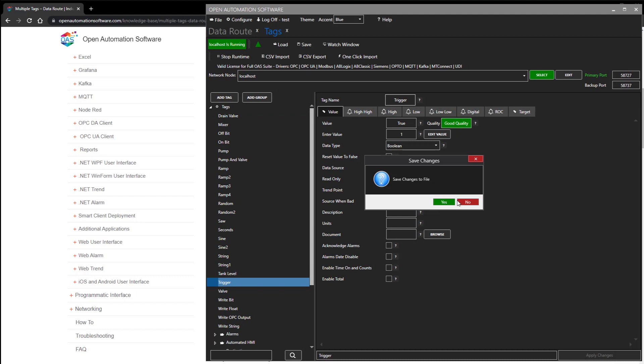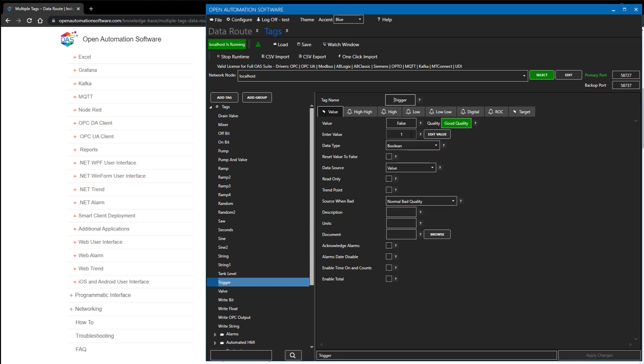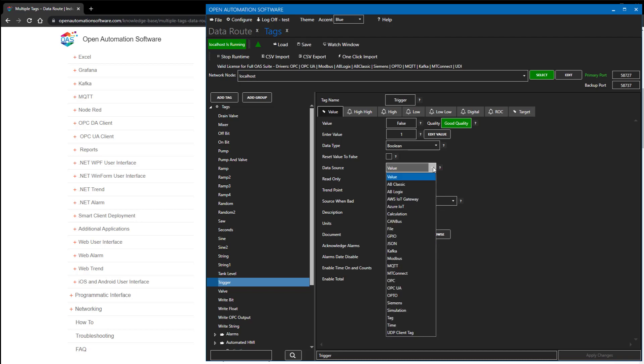Looking at the tags and the trigger tag, its current value was already true and then flashed to false. Setting it to true again — after five seconds (our time delay), it will be written back as false. If that data source were connected to a controller, such as a Siemens Boolean variable, an Allen Bradley variable, or a Modbus coil status, it would write that value to the controller itself.